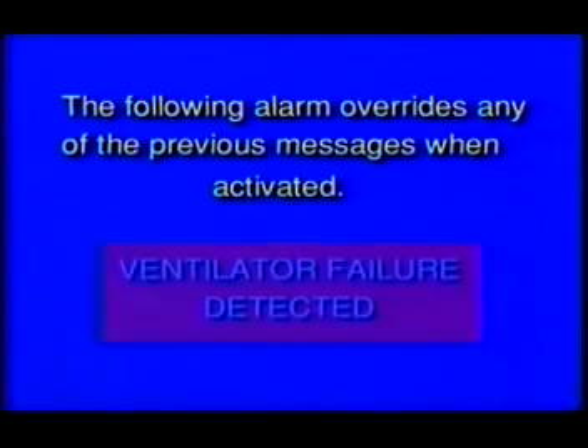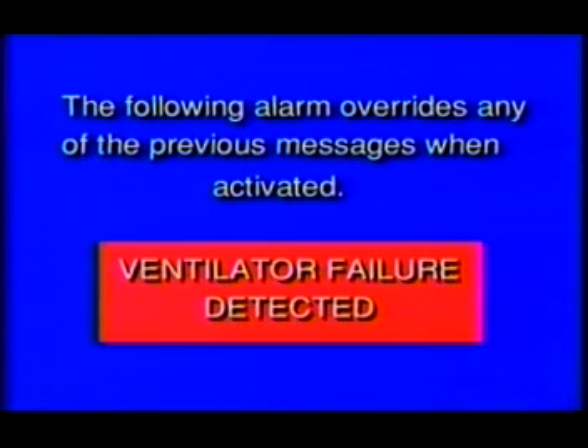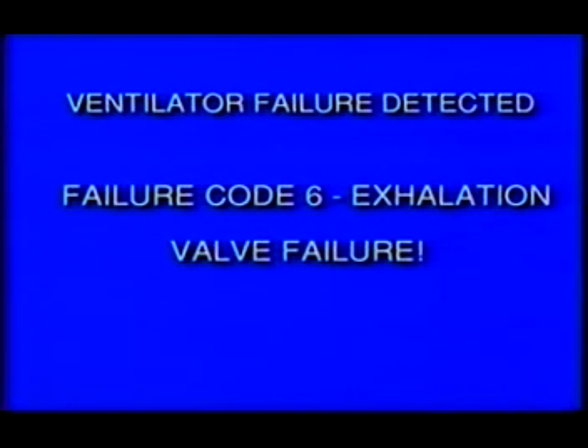The following alarm overrides any of the previous messages when activated. Ventilator failure detected. This alarm message is followed by one of the following statements. Failure code 1. Self-check failure. Failure code 2. No gas and compressor failure. Failure code 3. Total flow backup check failure. Failure code 4, excessive airway pressure. Failure code 5, memory check failure. Failure code 6, exhalation valve failure. Failure code 7, excessive negative pressure.